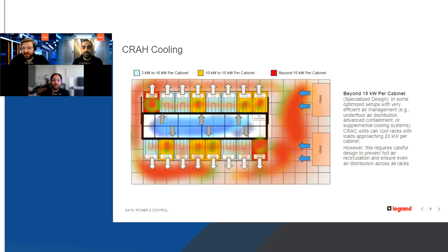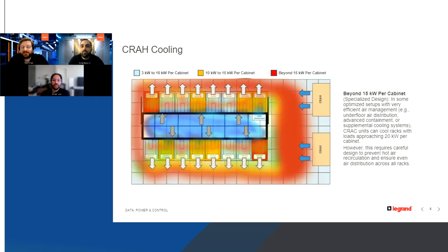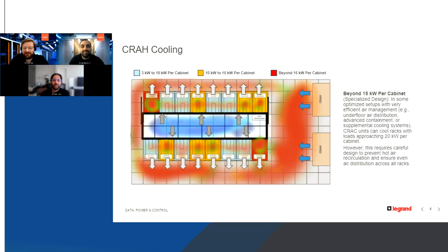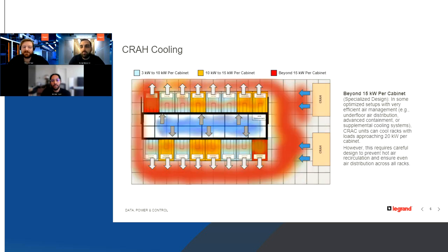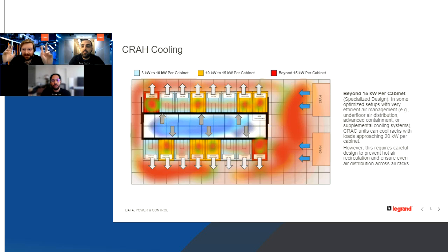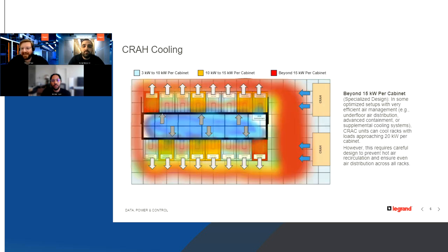Oh yeah, and thanks for bringing in the topic of cabinets, because it is absolutely true that you have to think about this as well. Think about the size of a cabinet. Think about the future, and for example, a 600 kilowatt cabinet with the higher demand in power. It is impossible to fit in, because you need the space for the PDUs. And if you potentially think about on-chip cooling, you need to place the manifold somewhere to distribute the water within the cabinet. So you even have to think about the easy things like the dimensions of your cabinet to be safe. So plan a step ahead.